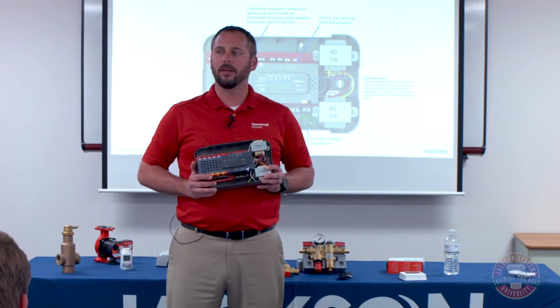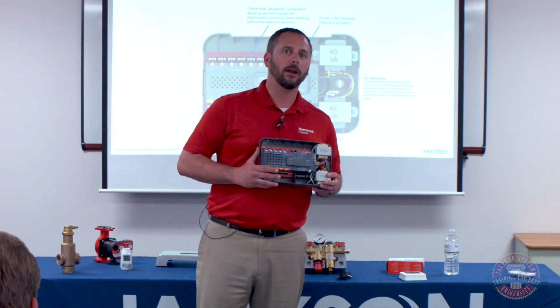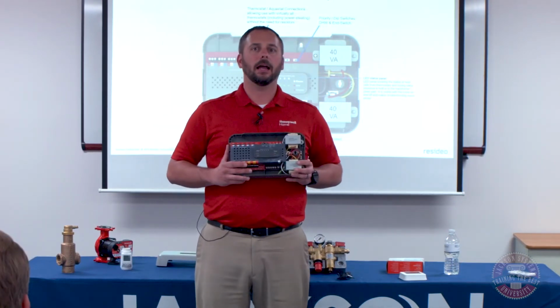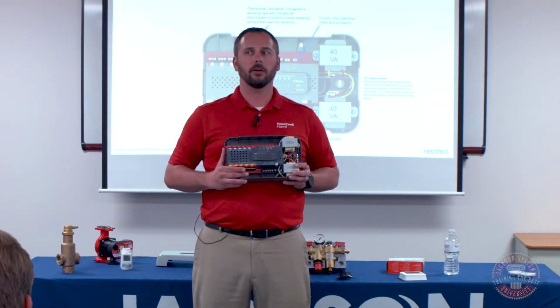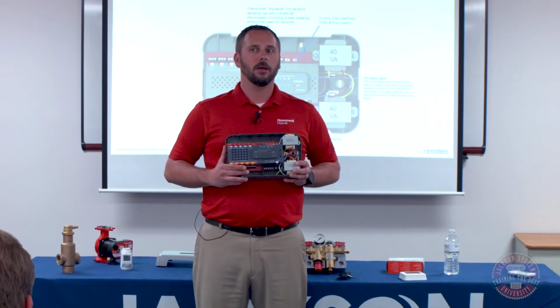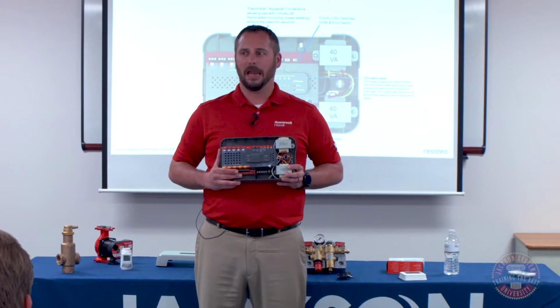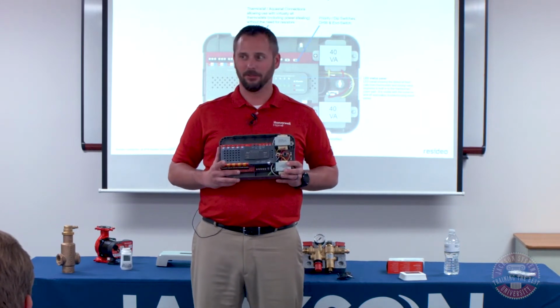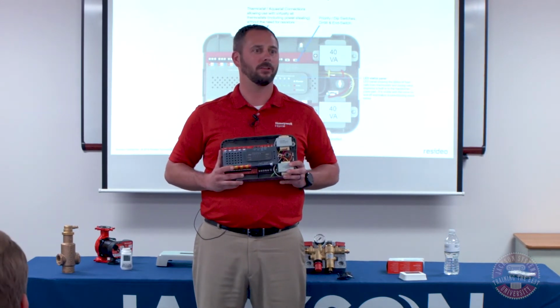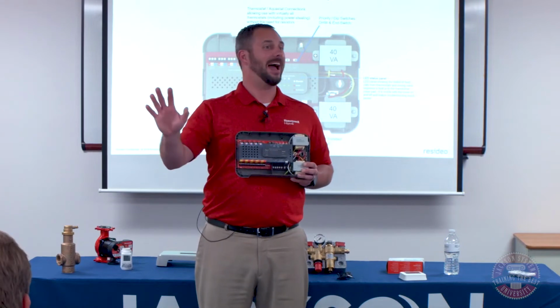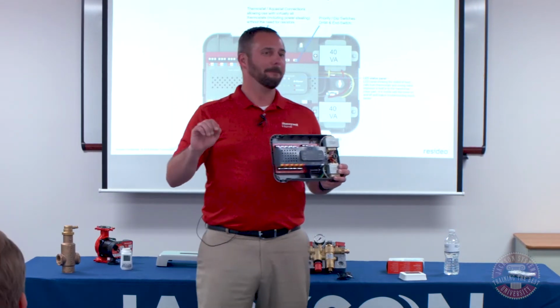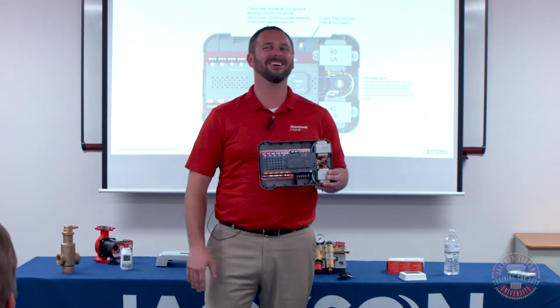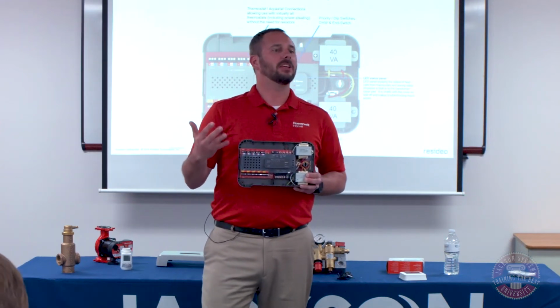And the reason I say that is I have helped people wire stuff in the field, and I have seen brand new thermostat wire that gets run behind a house. Everything gets sheetrocked, painted, etc. Then it's time to hook up the thermostat, and guess what? One of the wires is busted. We have a solution for that. Don't worry, but it's very expensive. So I always recommend running at least 4.